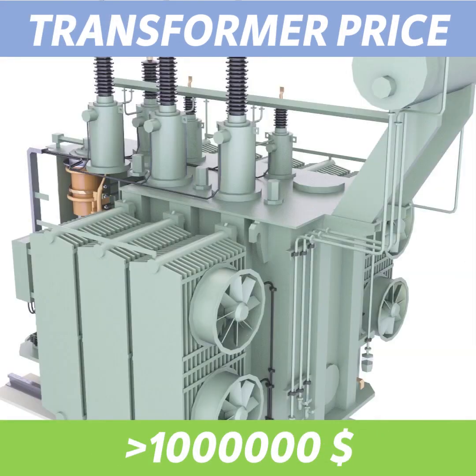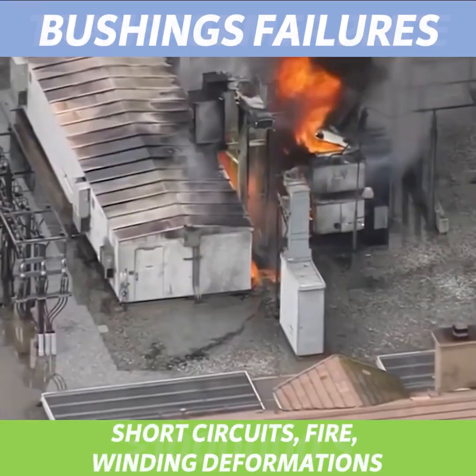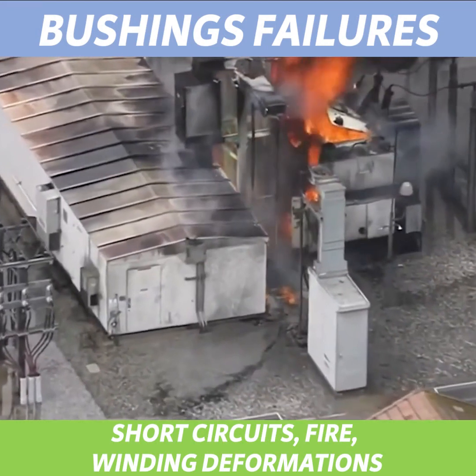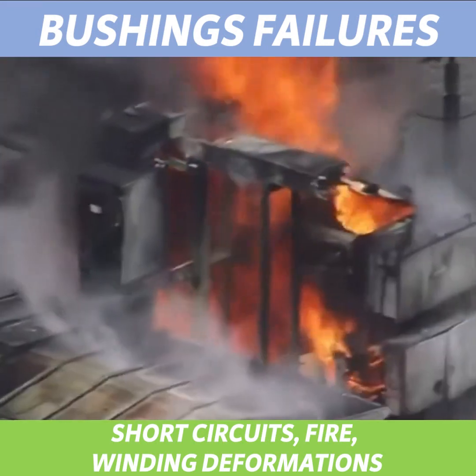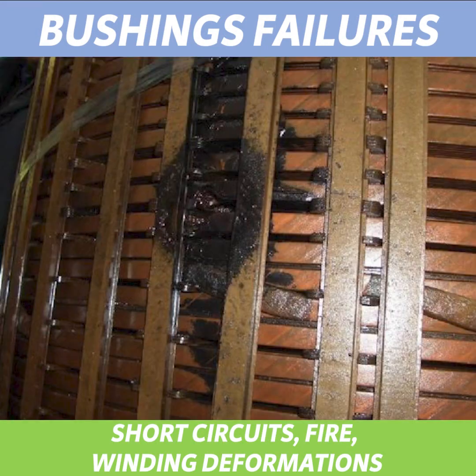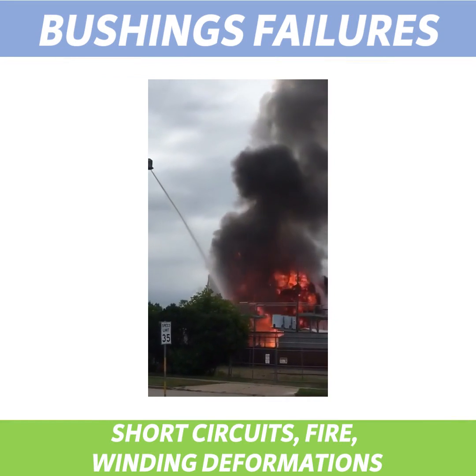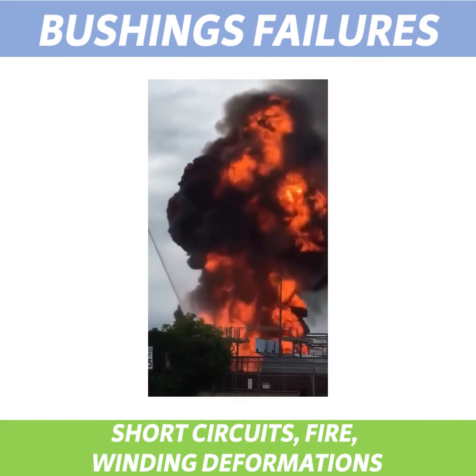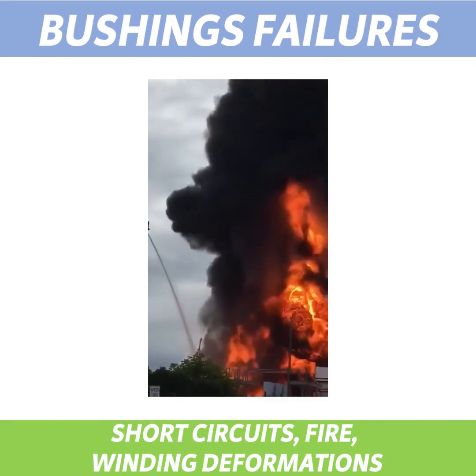Transformer price. A typical power transformer price is greater than $1 million US. Despite being relatively cheap compared to the transformer value, bushing failure quite often causes short circuits, which results in windings and core deformations and/or transformer fire. While some bushing problems can be revealed with regular testing, quite often faults occur between testing intervals.